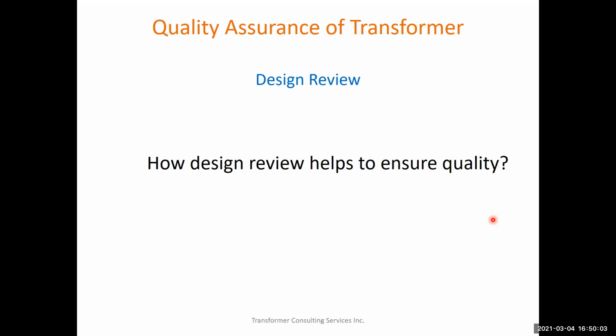So now at the design review stage, what we look at is whether the design is aggressive or not. If the factory quality is not good - let's say the factory is not fully climate controlled, or the factory floor is not clean - in that case, in the design, we try to force the manufacturer to be more conservative in the design. That's the whole purpose: to ensure the quality of the transformer.